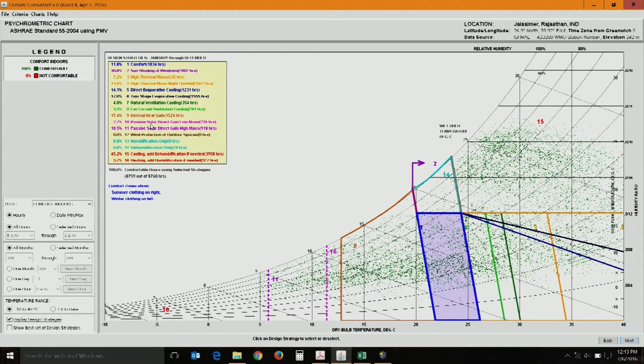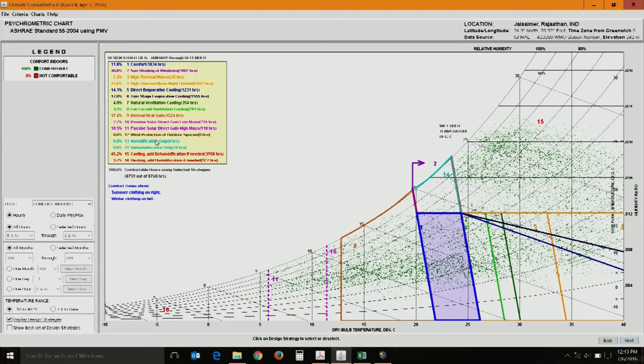Direct evaporative cooling — using water bodies around buildings, for example — is effective in dry seasons when temperatures are high but humidity ratio and relative humidity are low. Two-stage evaporative cooling works for slightly higher moisture content. Natural ventilation cooling with good cross ventilation is effective up to around 30°C and 40–50% relative humidity. Further strategies include passive direct solar heat gain for colder climates or seasons, and passive direct heat gain combined with high thermal mass, which extends comfort to higher temperatures.